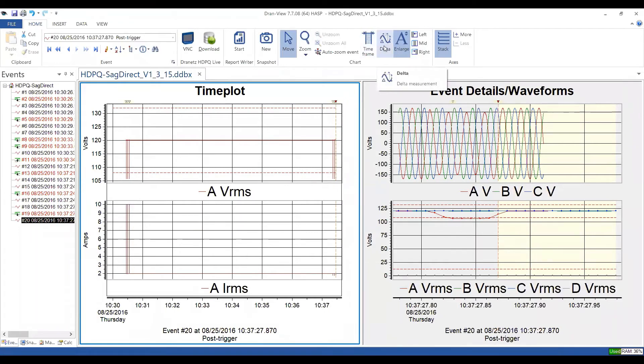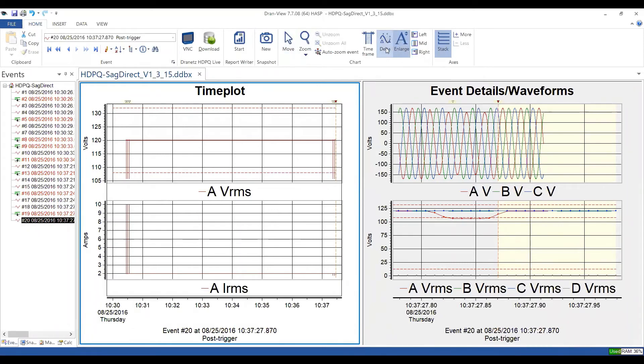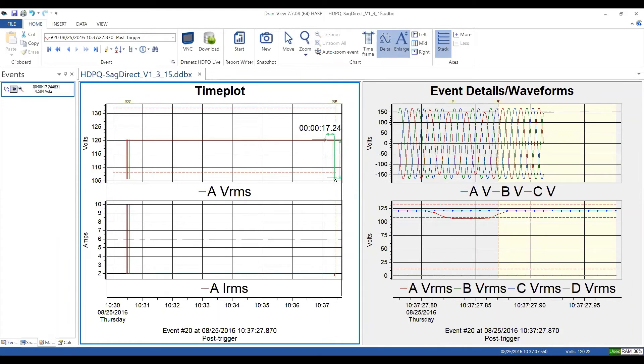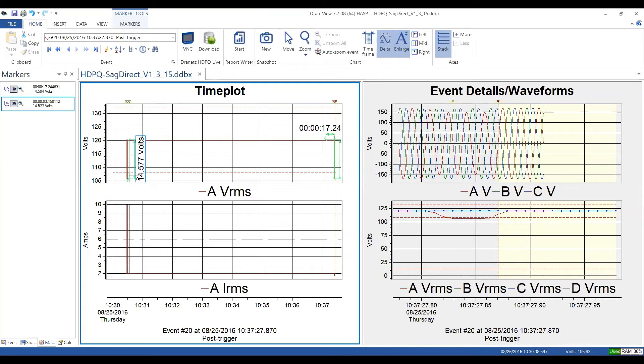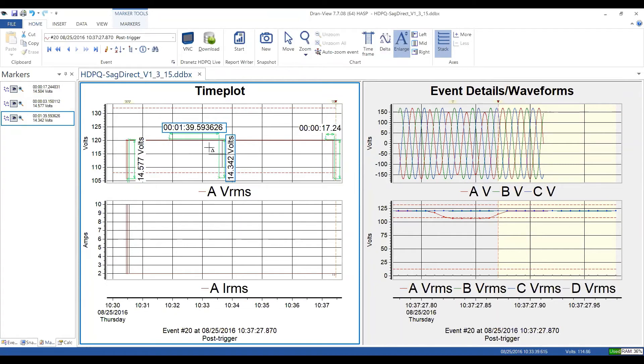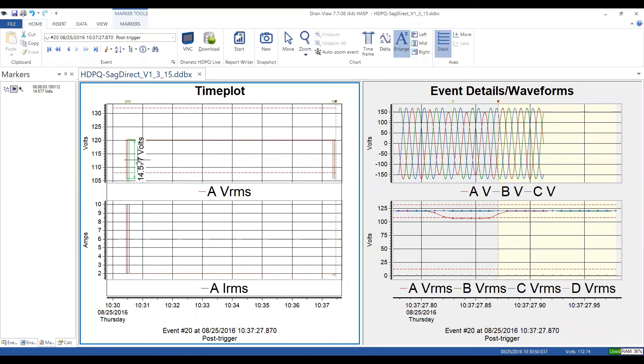You have a delta tool. If you want to look at the difference between two points — for example, how far a SAG dropped from its normal condition — you pick up the delta tool, click and hold one point, then click and drag to the other point. You can see the drop displayed, in this case 14.57 volts. You can draw the delta tool both left and right and see the difference in the x-axis in time and y-axis in the parameter — here, voltage. To delete them, just right-click and delete individually.